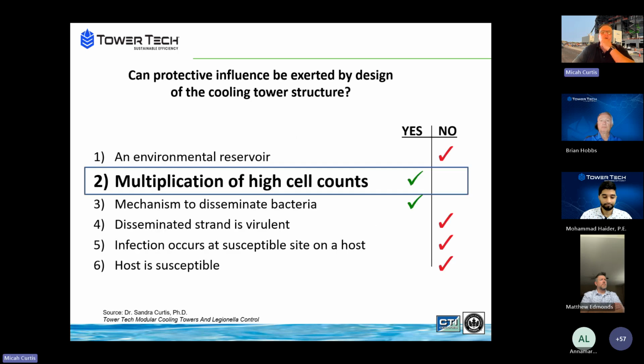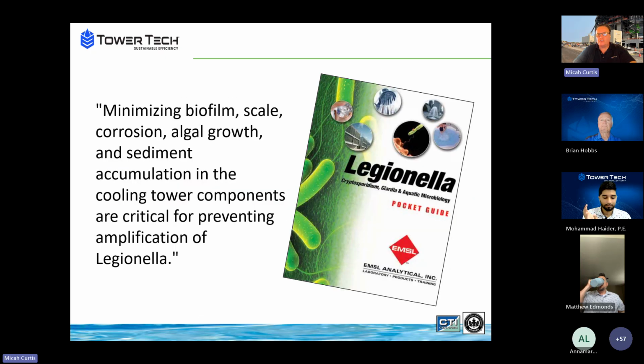Okay. And what we're going to discuss here shortly is, of the 6 events, if you take one of those events out of that equation, then Legionnaire's disease does not occur. So what we're going to be focusing on the next 15, 20 minutes is affecting the multiplication of these high cell counts. Most systems have maybe some level of Legionella bacteria in them. It's when they multiply and go crazy that there becomes a problem in this equation. And then, of course, the mechanism to disseminate the bacteria. That's probably a fan of some sort blowing that drift into the environment near susceptible hosts. So if we can affect those 2 items, then you reduce, possibly eliminate, the opportunity for Legionnaire's disease to occur.